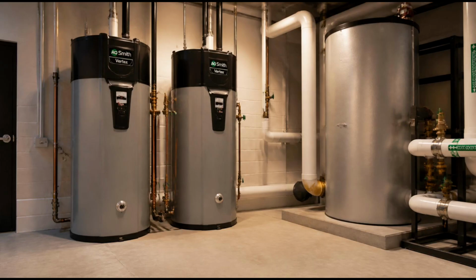Larger buildings often use a different approach. Commercial boilers, high-capacity heating systems that can produce large volumes of hot water efficiently, serve as the heat source, and their output is distributed through a network of piping and heat exchangers that warm the potable water supply. Boiler systems are well suited to buildings with high and variable hot water demand, where a single storage tank would be depleted quickly and insufficient to keep up.